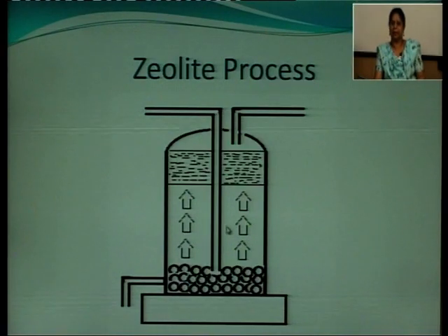When we pass brine solution and remove the waste from this lower tap, then the whole of the calcium and the magnesium ions are converted into calcium or magnesium chlorides and are removed with wastewater, and the permutit is again regenerated, or we can say that we can use it again and again by washing it with sodium chloride.